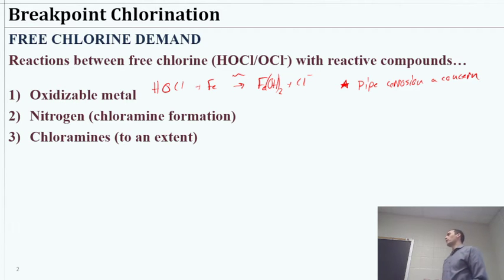Now, there's a few things we do for that. Namely, we add some corrosion control, make it less likely for the pipes themselves to be vulnerable to it. And we also typically operate our distribution systems in a manner that we expect to have mineralization, so mineral deposits slowly over time, which will eventually choke the pipes and constrict them and prevent them from working.